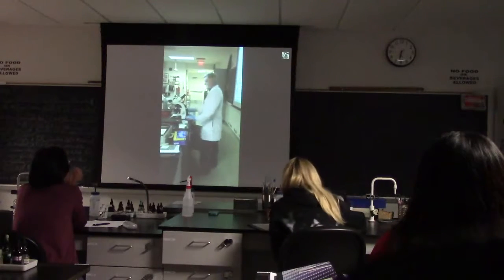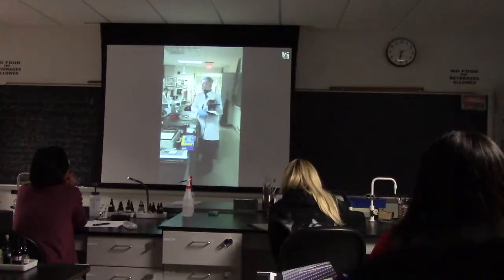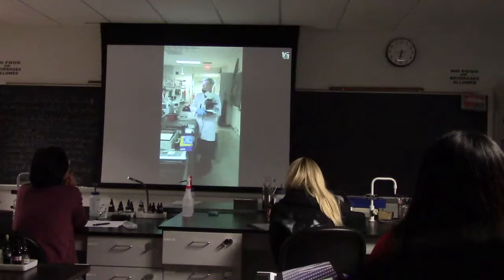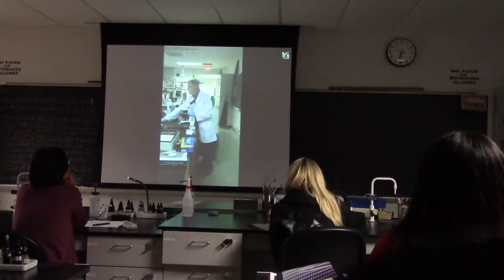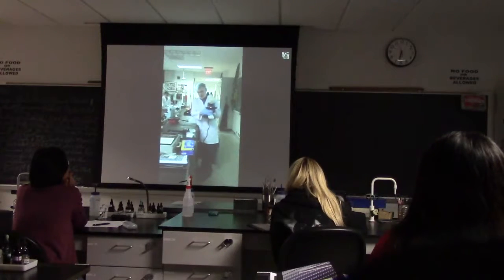You are going to get your microscope out and carry it over, and first thing you check this little button here, the round wheel, and make sure it's back all the way to you, clicked off. Then you plug it in, and then you turn the power to 90%. Then you bring the condenser up and open the iris diaphragm almost fully.